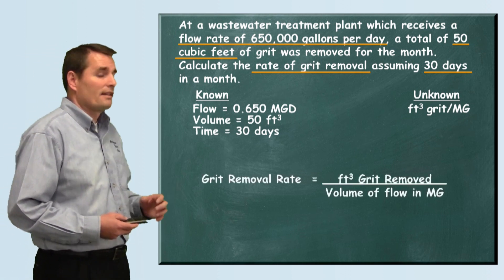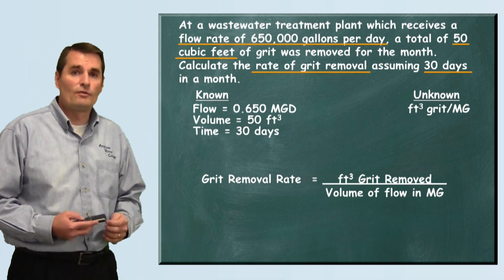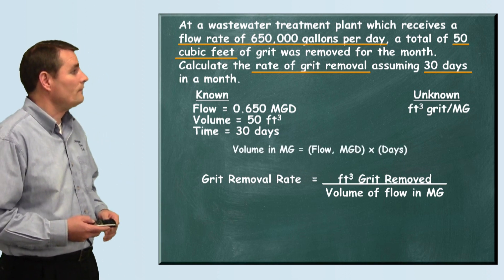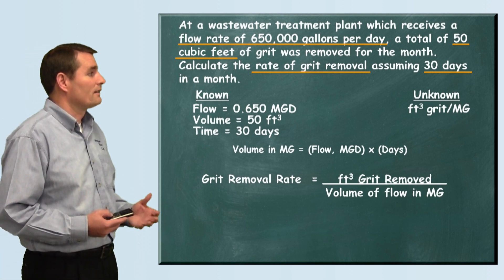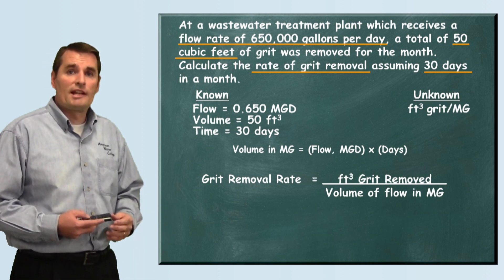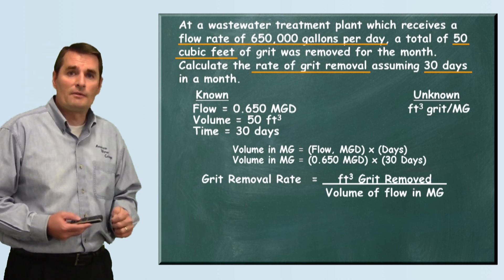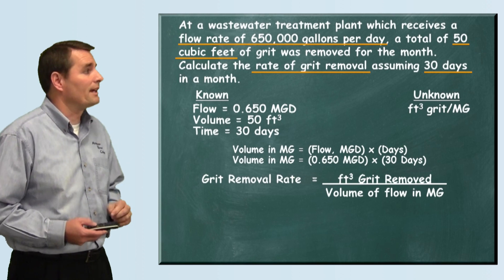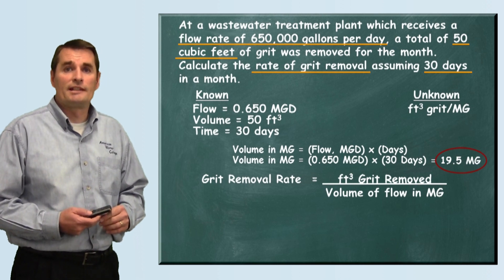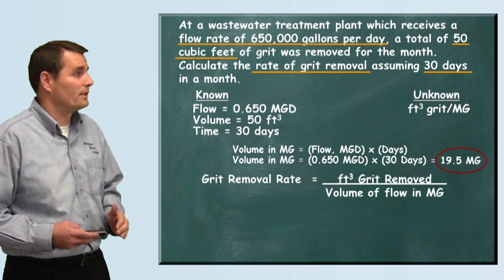Now that we have this information, let's set this up using a formula. The grit removal rate equals the cubic feet of grit removed divided by the volume of flow in millions of gallons. To find our volume over the 30-day period, we take our average daily flow of 0.650 MGD and multiply by 30 days, giving us a total flow of 19.5 million gallons.